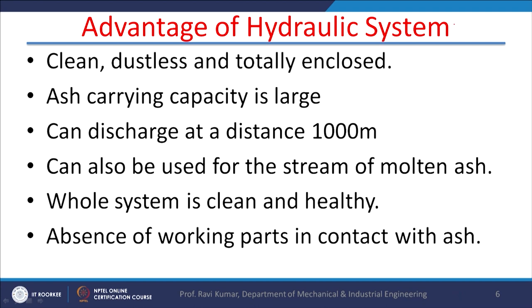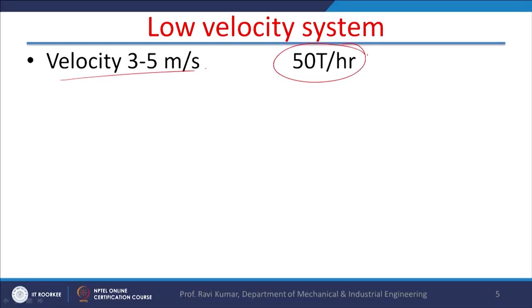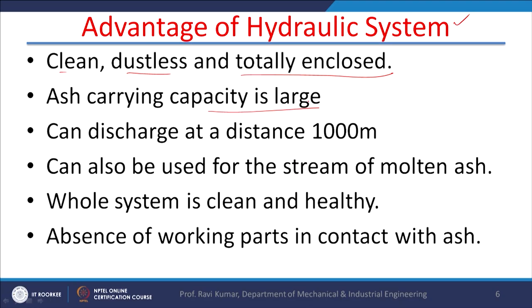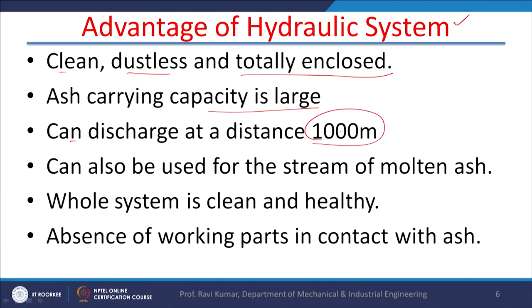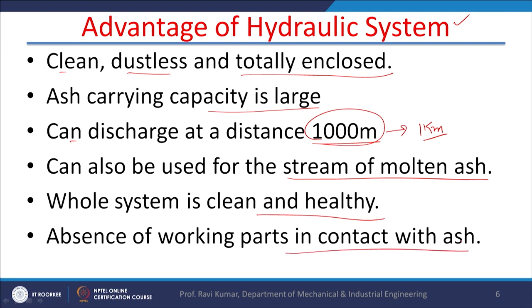The hydraulic system has certain advantages. First, it is clean — dustless and totally enclosed. Ash carrying capacity is large; unlike the mechanical system, we can increase water velocity to carry more ash. Ash can be discharged at a distance of 1000 meters — 1 kilometer — away from the plant, which is a major benefit. It can be used for a stream of molten ash, and there are no working parts in contact with the ash, which is another advantage.